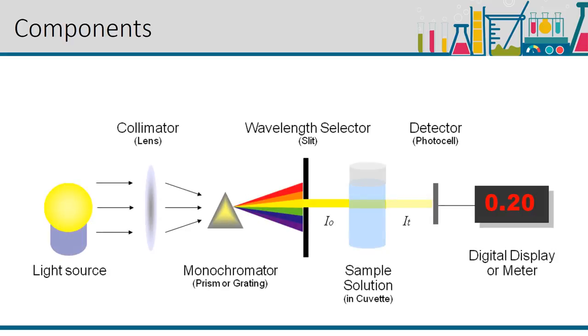In a colorimeter, a beam of light with a specific wavelength is passed through a solution via a series of lenses, which navigate the colored light to the measuring device. This analyzes the color compared to an existing standard. A microprocessor then calculates the absorbance or percent transmittance.